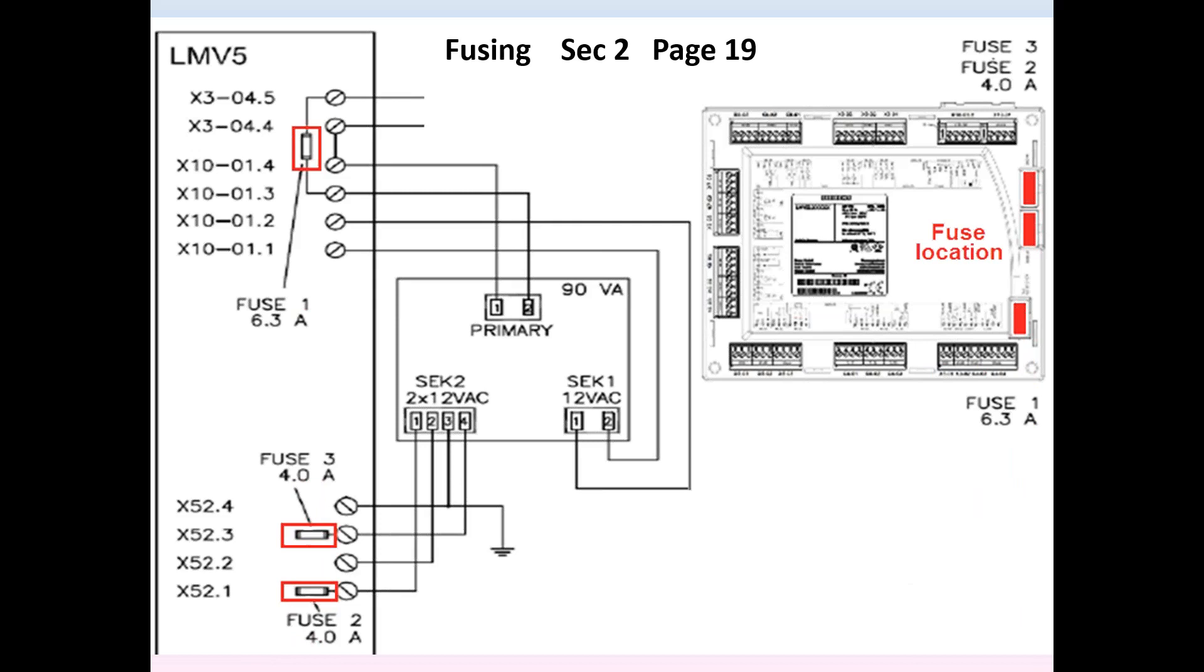And finally, I'd like to point out a common wiring error from the transformer SEK2 to LMV-5's X52. Note the crossover. Specifically, one goes to one, two goes to two, three goes to four, and four goes to three.